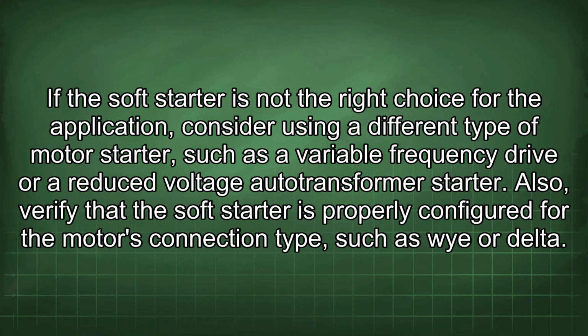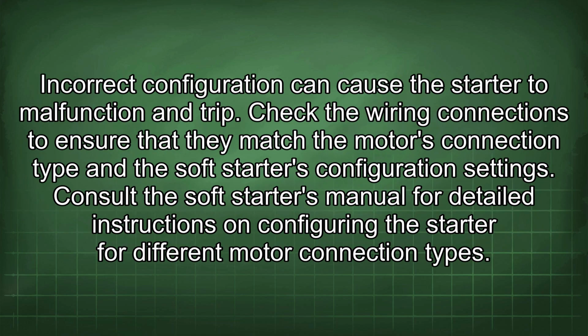Also, verify that the soft starter is properly configured for the motor's connection type, such as Y or Delta. Incorrect configuration can cause the starter to malfunction and trip. Check the wiring connections to ensure that they match the motor's connection type and the soft starter's configuration settings. Consult the soft starter's manual for detailed instructions on configuring the starter for different motor connection types.